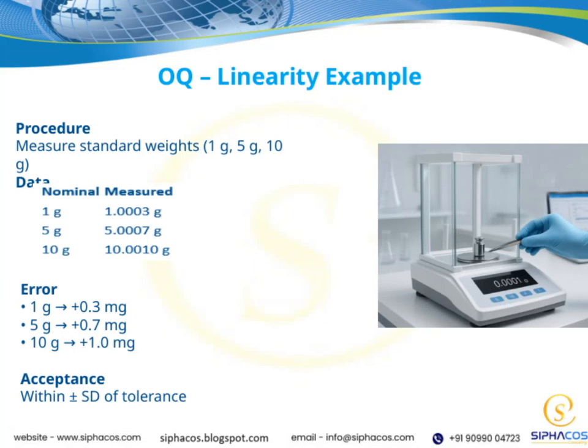Let's take a closer look at the error measurements. For example, when we have a 1 gram weight, the error is about plus 0.3 milligrams. If we move up to a 5 gram weight, the error increases slightly to around plus 0.7 milligrams. And for 10 grams, the error is approximately plus 1.0 milligrams. These numbers highlight how measurement errors can vary depending on the weight we're measuring. It's important to understand that within our process, we accept measurements that fall within the acceptable range, which is typically within plus or minus 1 standard deviation of the tolerance.